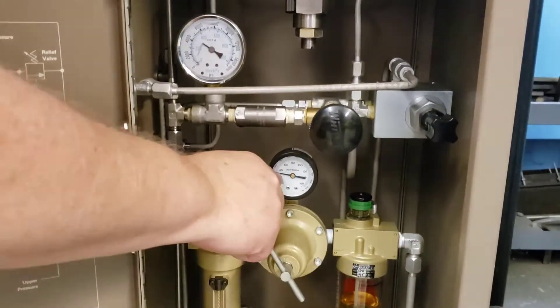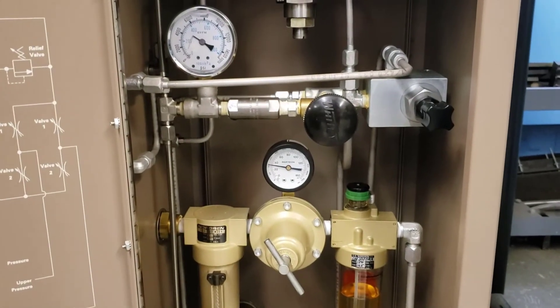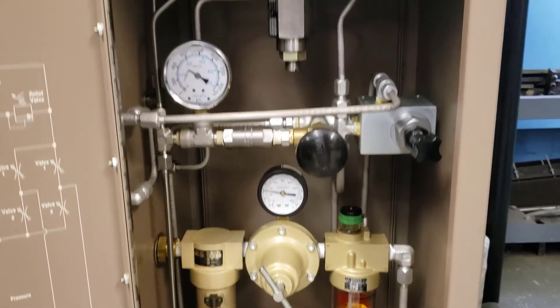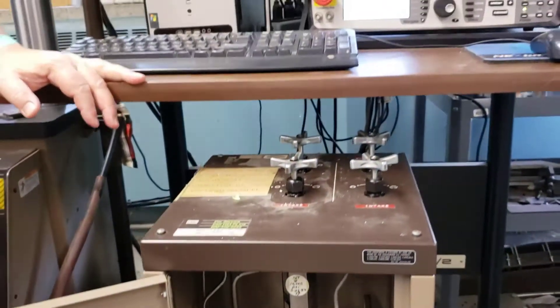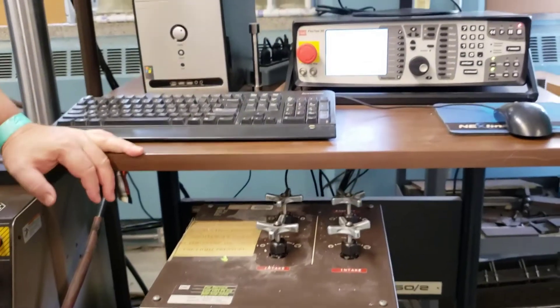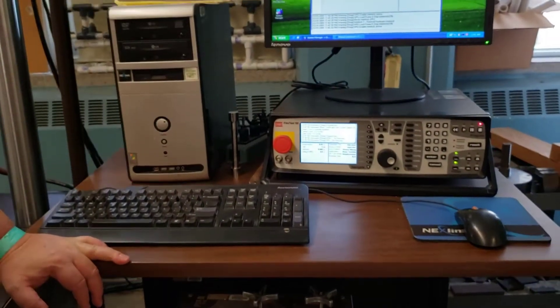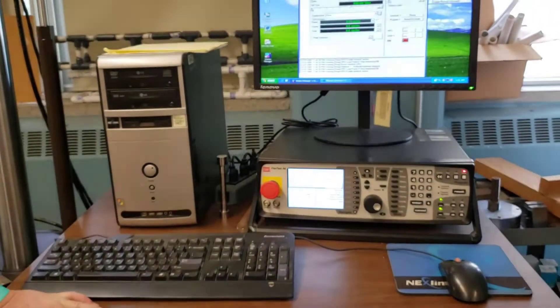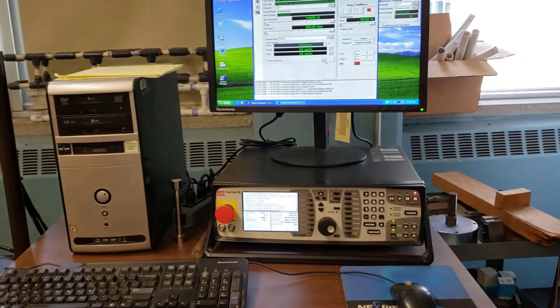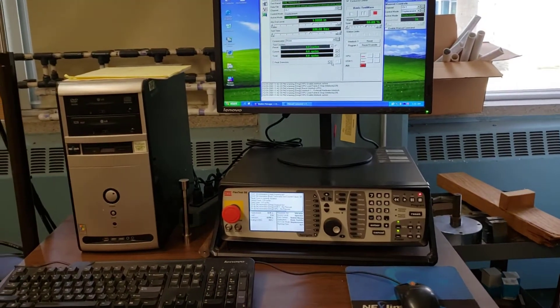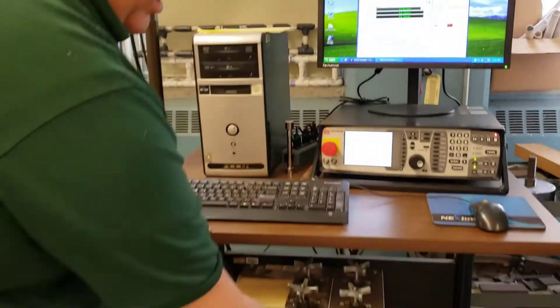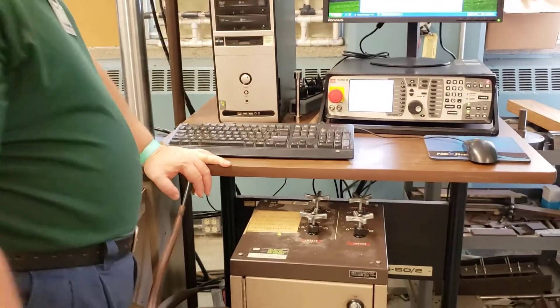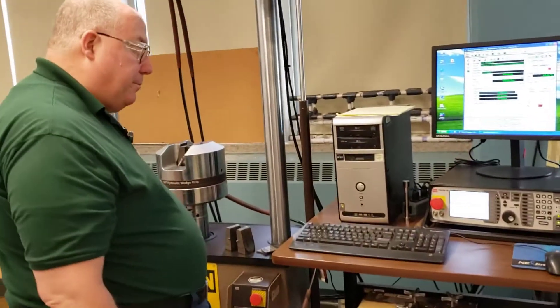The higher you set this, the tighter these grips will squeeze. For steel, 30 is more than enough and it'll hold it just fine. It won't slip. The point is you don't want the sample slipping while we perform the test. But you don't want to go too high either because you just put more work on the system.